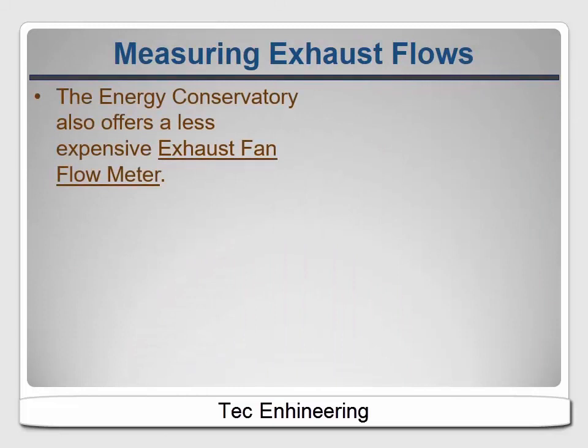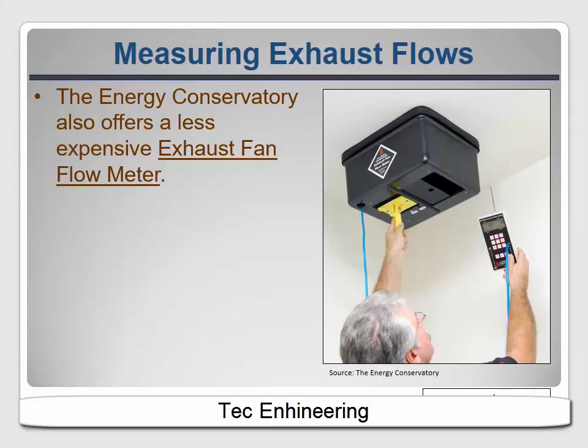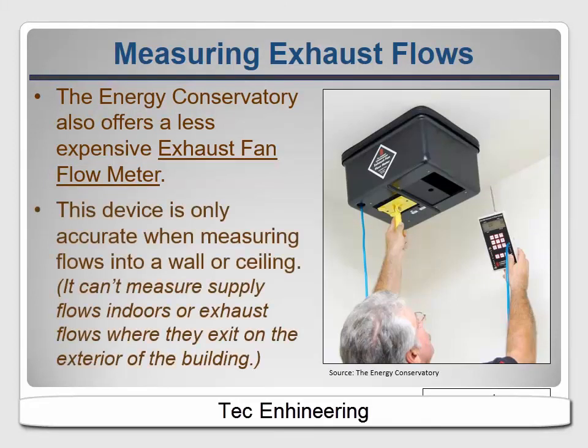The Energy Conservatory also offers a lower-cost alternative they call an exhaust fan flow meter. It's basically a plastic box with a gasket and an adjustable opening that works in conjunction with a digital pressure and flow gauge like the DG700. If you already own the gauge because it came with a blower door or duct blaster, you can buy the plastic box for $150. It's lightweight and easy to use, but it's only accurate for measuring exhaust air flowing into it — it won't give you a good reading for air coming out of a register.